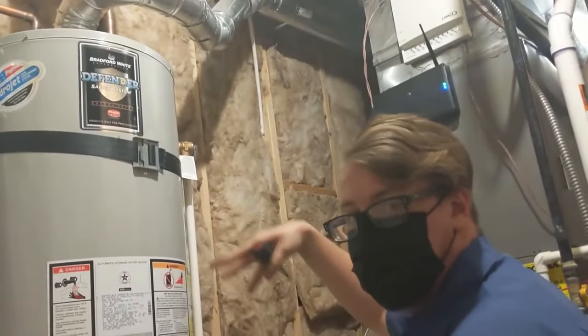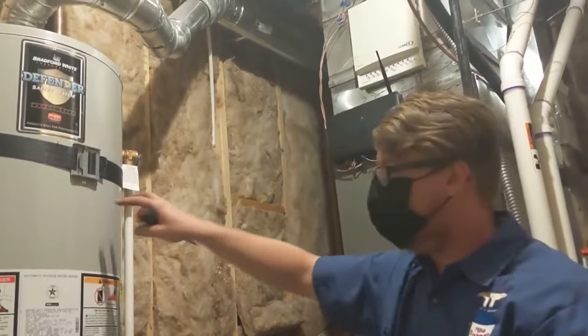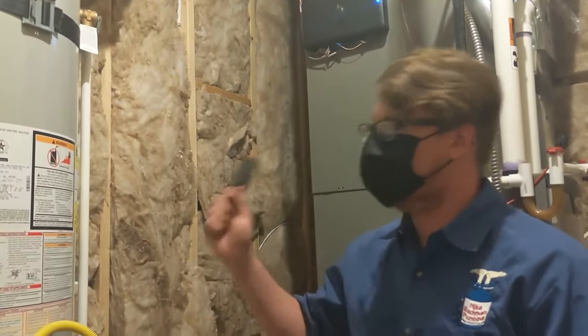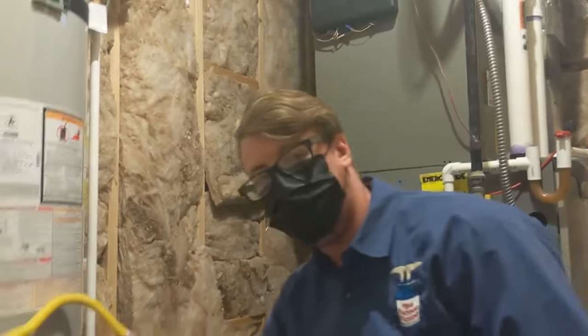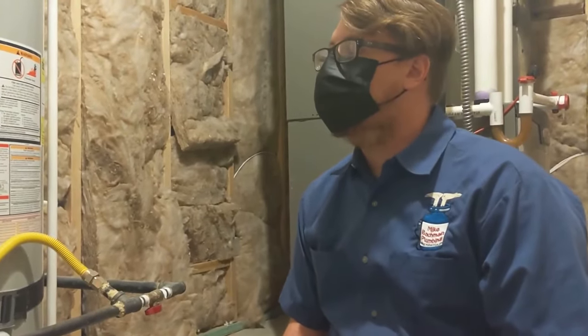You've got 50 or 40 gallons in each tank, and your water supply will keep refilling it. So you could fill that five-gallon bucket a million times and never fully clean it out — unless you turn the water supply off first. If you turn the water off, you'd only get about 40 gallons total — eight buckets. But you actually want to leave the water on; you want that pressure to push the sediment out, otherwise it could just clog your drain. Maintenance should be done once a year maximum, as recommended by the manufacturer — or maybe once every two years.